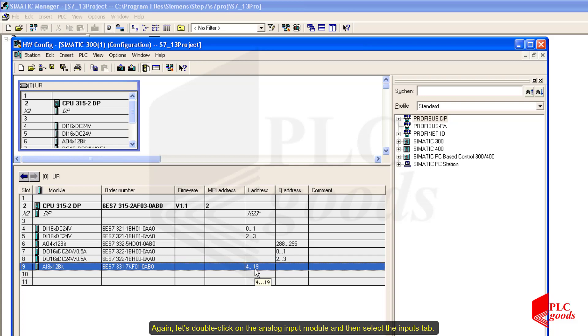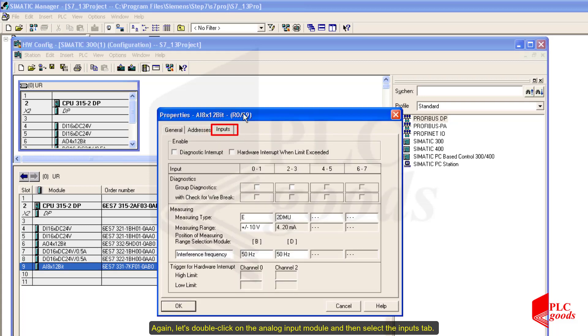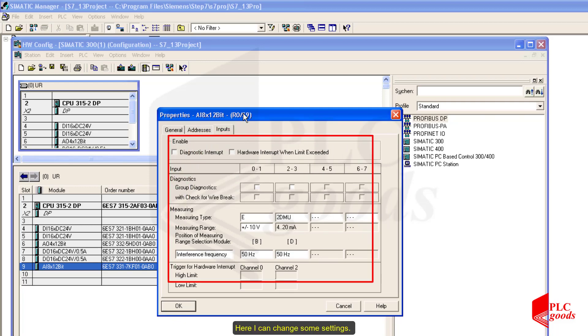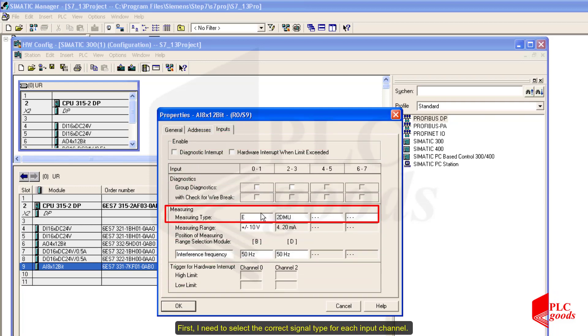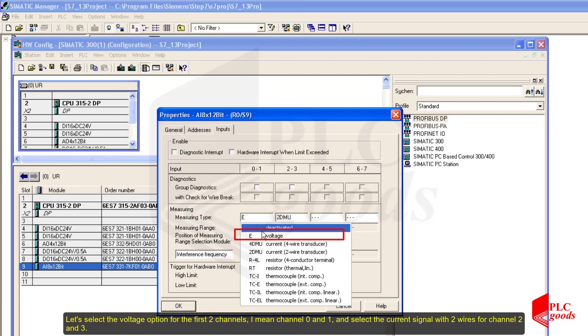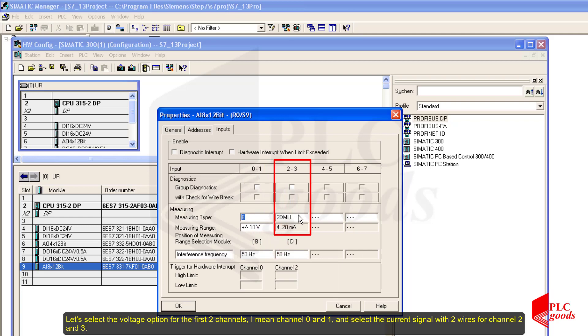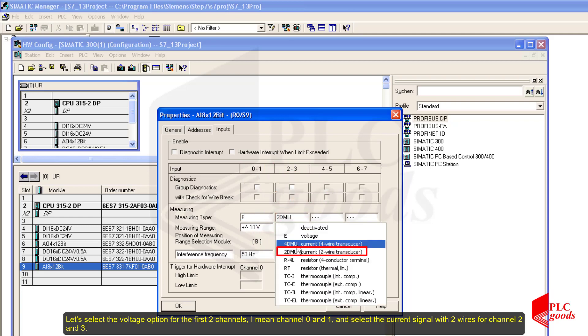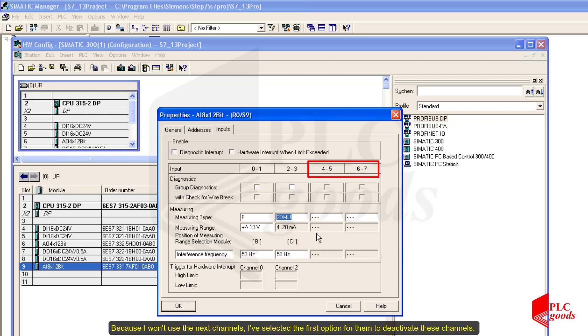Let's double click on the analog input module and select the input tab. Here I can change the settings. First I need to select the correct signal type for each input channel. I'll select the voltage option for the first two channels — channel 0 and 1 — and select the current signal with two wires for channels 2 and 3. For the remaining channels I've selected the deactivate option.